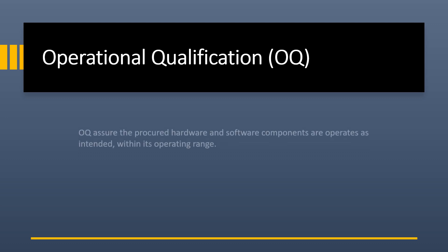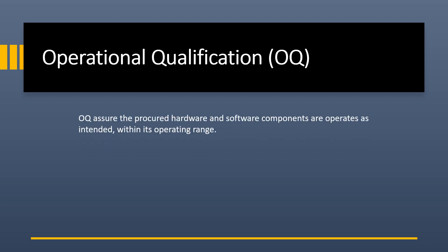Operational qualification assures that the procured hardware and software components operate as intended within their operating range. For example, in an HPLC instrument there is a column oven with an operating range of, say, 10 to 50 degrees Celsius.